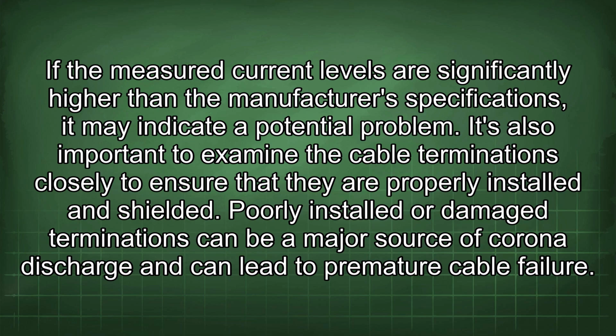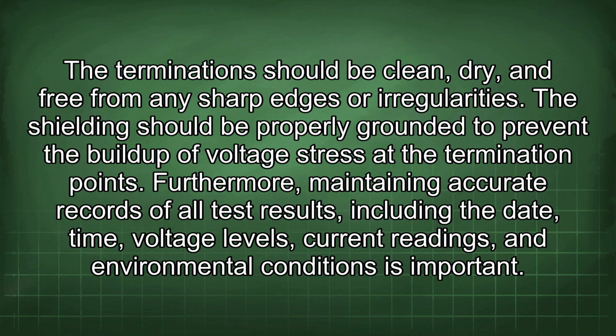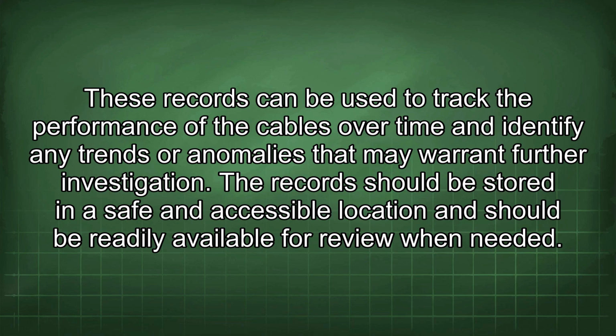It's also important to examine the cable terminations closely to ensure that they are properly installed and shielded. Poorly installed or damaged terminations can be a major source of corona discharge and can lead to premature cable failure. The terminations should be clean, dry, and free from any sharp edges or irregularities. The shielding should be properly grounded to prevent the buildup of voltage stress at the termination points. Furthermore, maintaining accurate records of all test results, including the date, time, voltage levels, current readings, and environmental conditions is important. These records can be used to track the performance of the cables over time and identify any trends or anomalies that may warrant further investigation. The record should be stored in a safe and accessible location and should be readily available for review when needed.